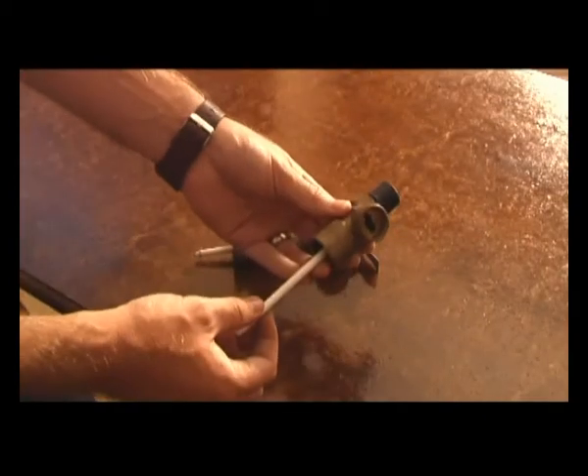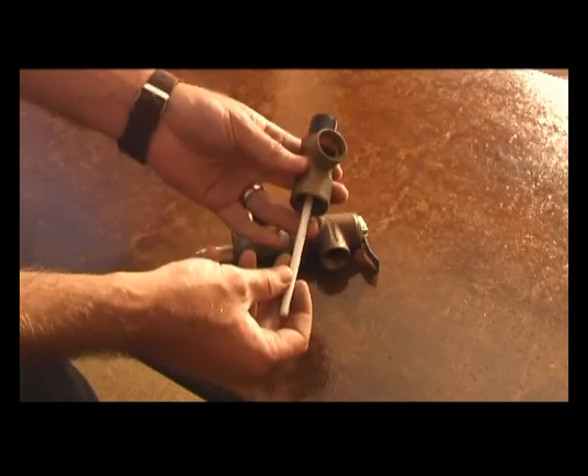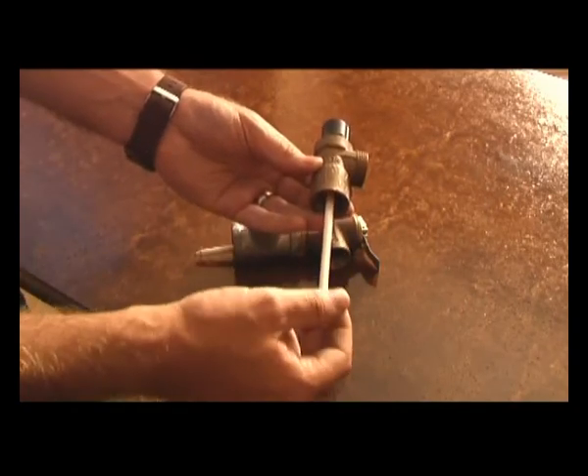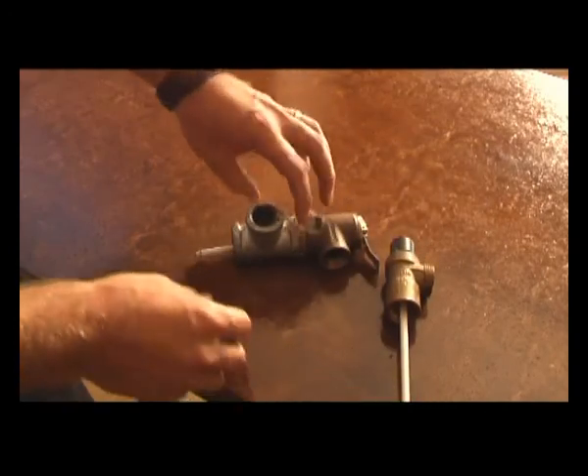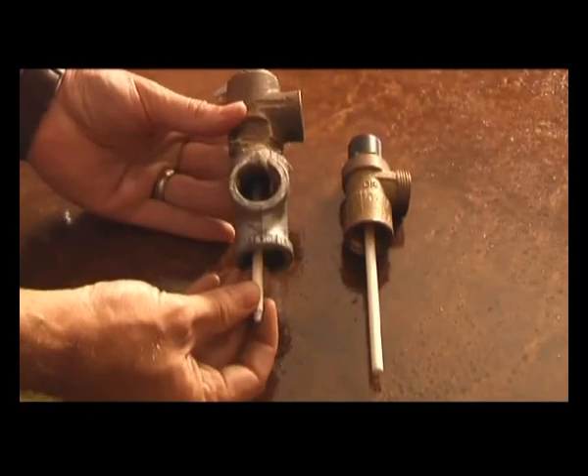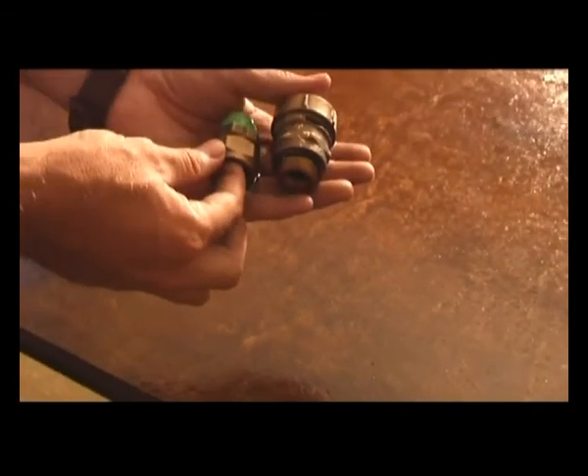A temperature and pressure valve has a probe inserted into the geyser which contains wax. As the water heats up the wax melts, and when the water reaches between 92 and 95 degrees Celsius the pin inside the probe pushes open a jumper, releases the boiling water and lets in cold water from the mains. SANS 10254 states that the probe of the T&P valve needs to be a minimum of 25% of its length inside the body of water being heated. In this case, someone attempted to make an extra port on the geyser but the probe will not enter the geyser as required.